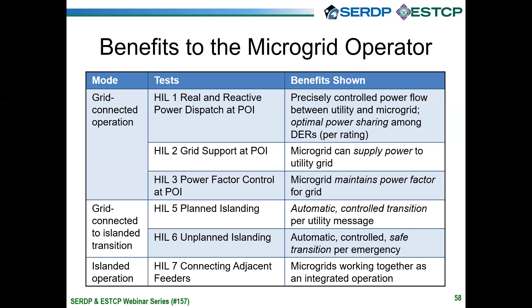Now, if you don't have enough power on the microgrid side and loads are still connected, sooner or later we have to do load shedding. So we have some algorithms we plan to evaluate and test, so that on the microgrid side we can also do load shedding automatically based on some priority scheme.